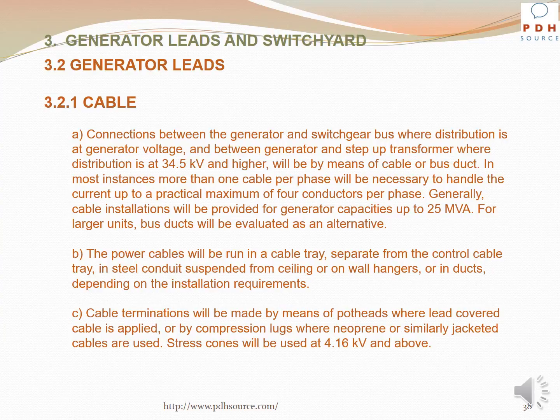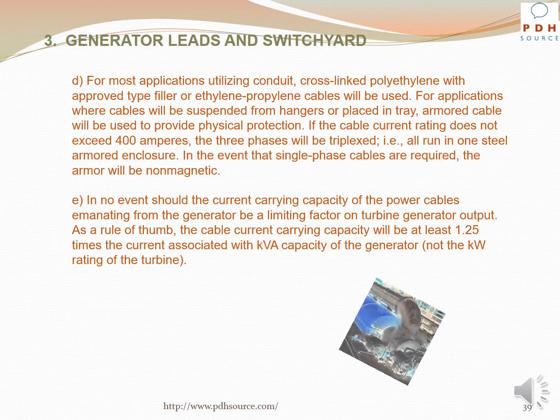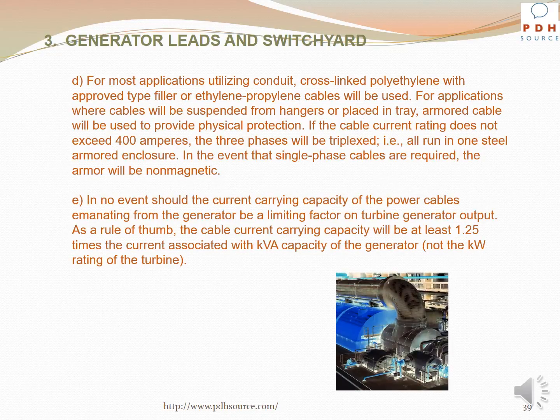The power cables will be run in a cable tray separate from the control cable tray, in steel conduits suspended from ceiling or on wall hangers or in ducts, depending on the installation requirements. Cable terminations will be made by means of potheads where lead-covered cable is applied, or by compression lugs where neoprene or similarly jacketed cables are used. Stress cones will be used at 4.16 kV and above. For most applications utilizing conduit, cross-linked polyethylene with approved type filler or ethylene propylene cables will be used.